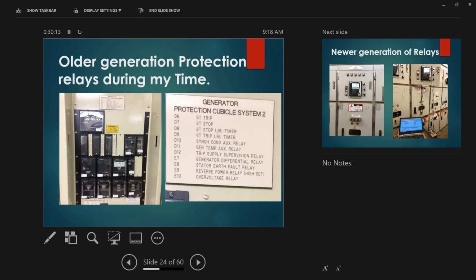In my time, you see this one guy here, it's only gas turbine trip. So all these boxes that you see only work as one function. You have trip supervision. It has some kind of label there anyway. And you have reverse power. It's an individual box, individual function. All of these labels here are labeled on that relay. There you can find those functions. What is the work of that relay? So it's an individual function. So you see the door of the panel is full of relays.